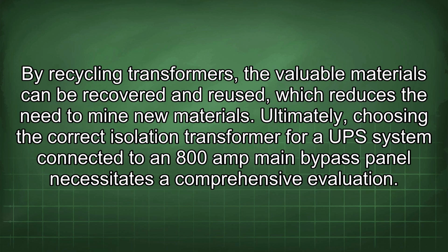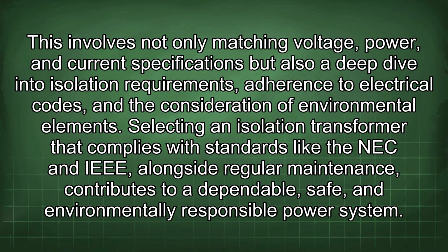Ultimately, choosing the correct isolation transformer for a UPS system connected to an 800 amp main bypass panel necessitates a comprehensive evaluation. This involves not only matching voltage, power, and current specifications, but also a deep dive into isolation requirements, adherence to electrical codes, and the consideration of environmental elements. Selecting an isolation transformer that complies with standards like the NEC and IEEE, alongside regular maintenance, contributes to a dependable, safe, and environmentally responsible power system.